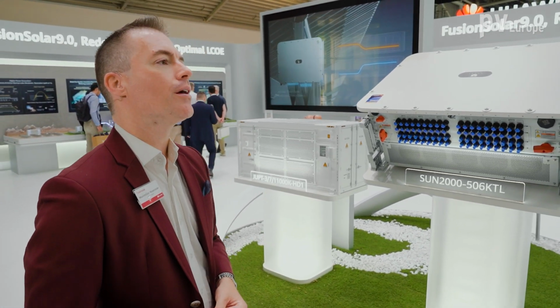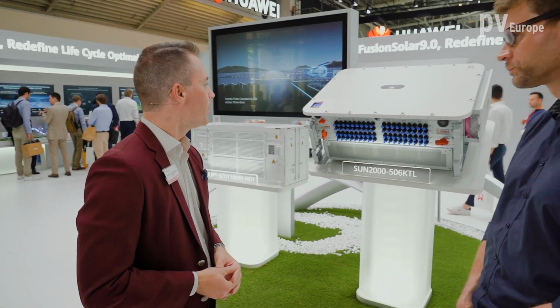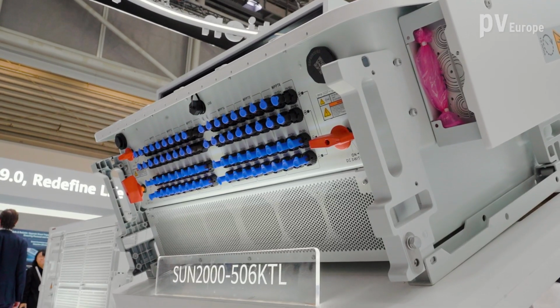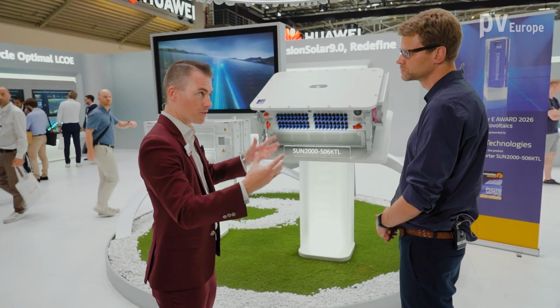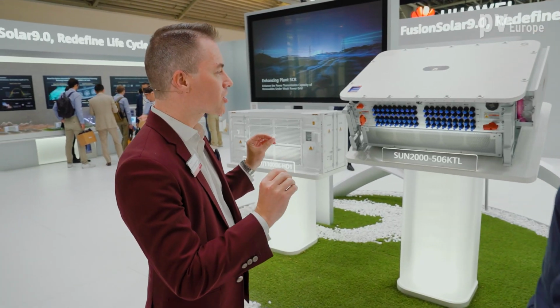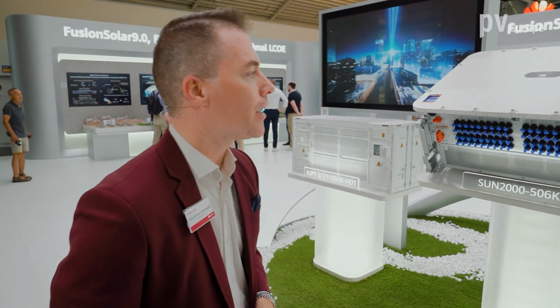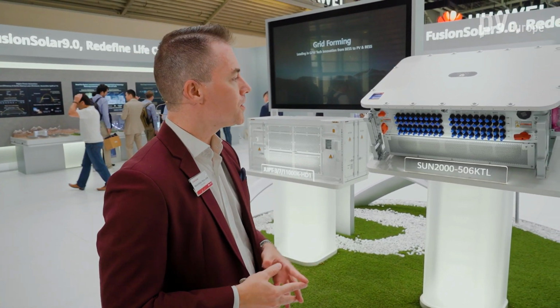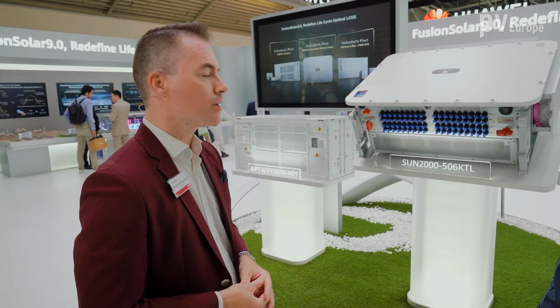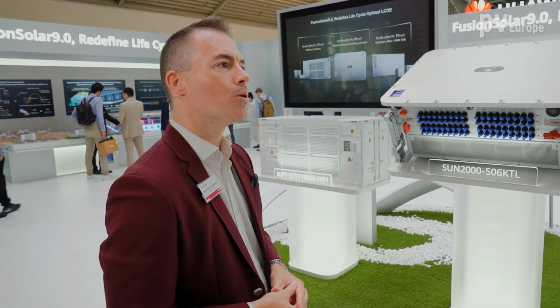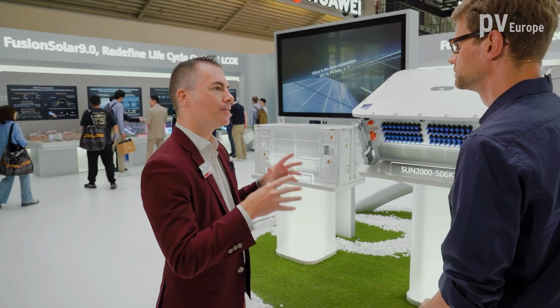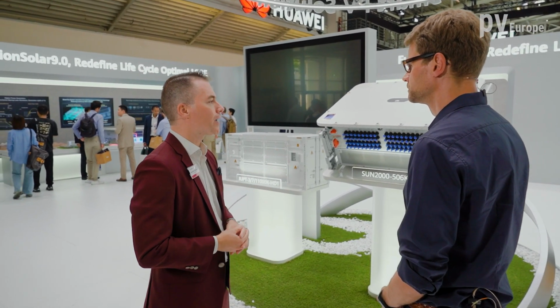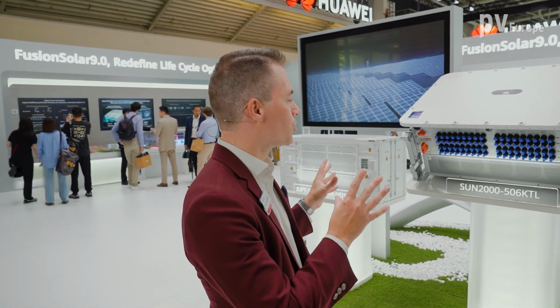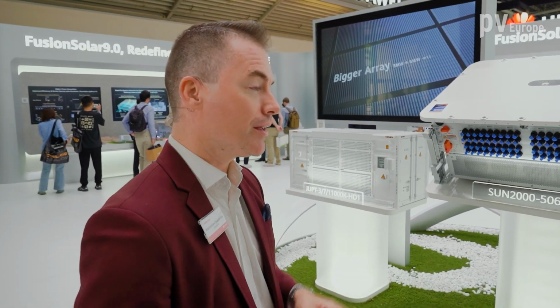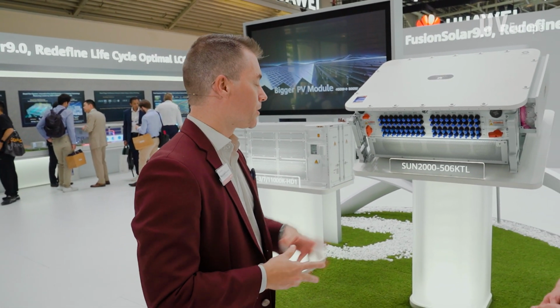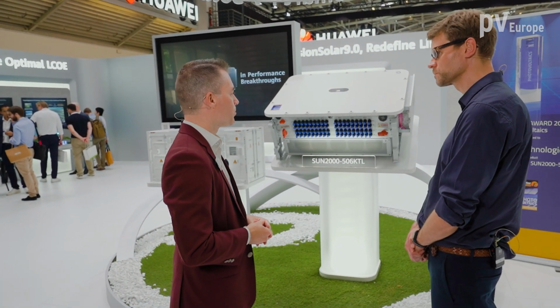So what are we doing with the 506 KTL? It's the most power dense PV inverter and our flagship model currently that is globally available. If you look at the size of this system compared to the 330 KTL, the predecessor machine, we're slightly increasing the size as well as the weight. How did we achieve that? With two different ideas. One, we completely redefined the internal cooling system. In the past it was fan-based. Now we installed a heat pipe system which will bring down the temperature of the chipsets rapidly, and we can therefore reduce the size of the system comparably by almost 50% if we would have just increased the power factor, because the power rating of the system is now 50% higher than the predecessor one.